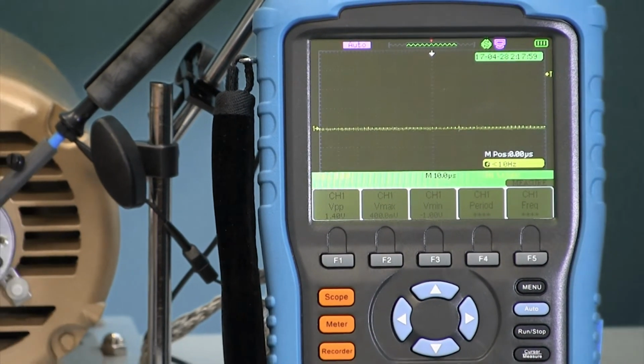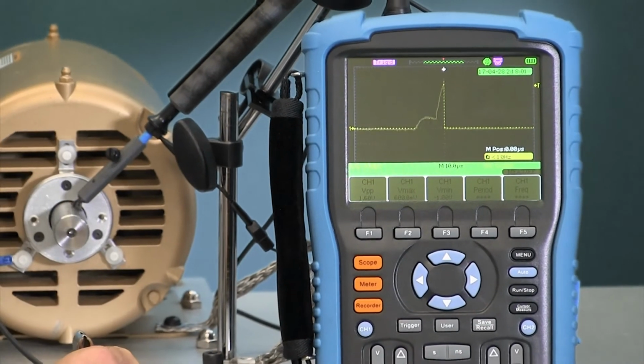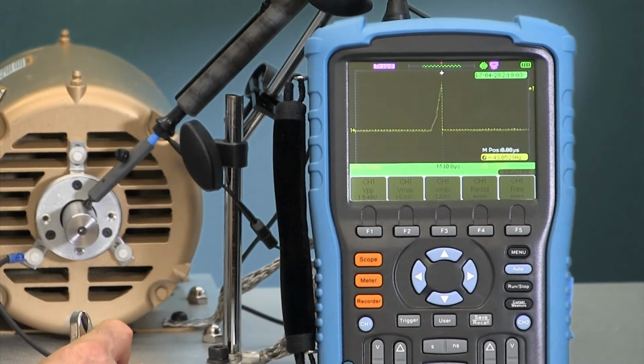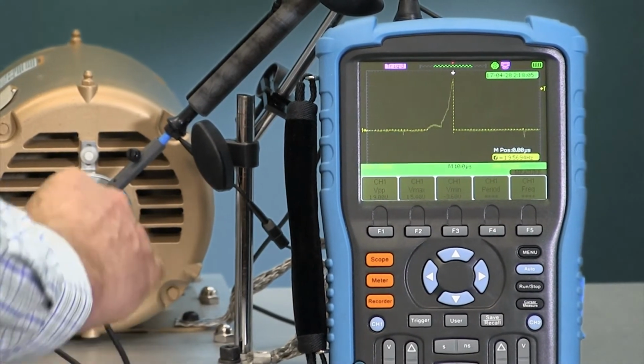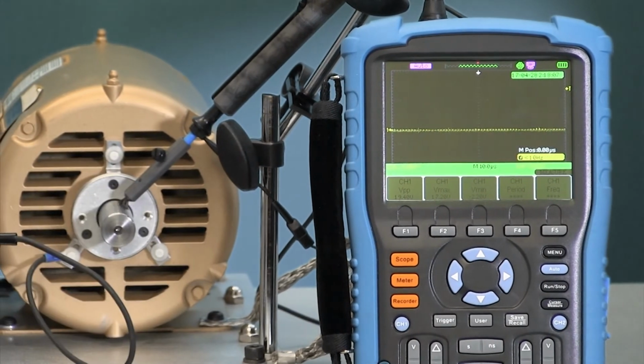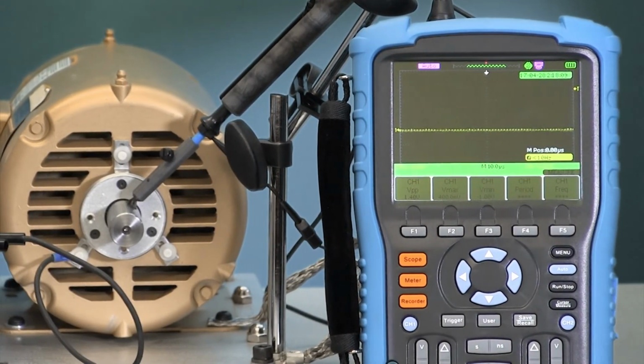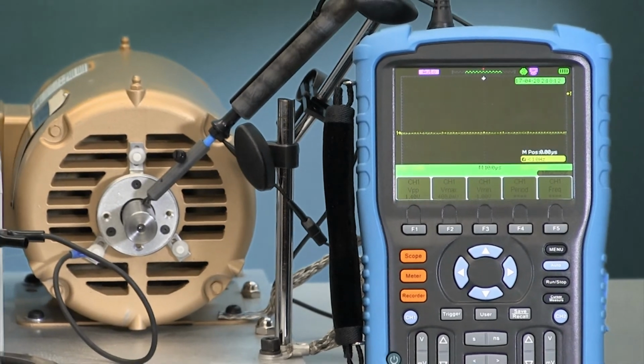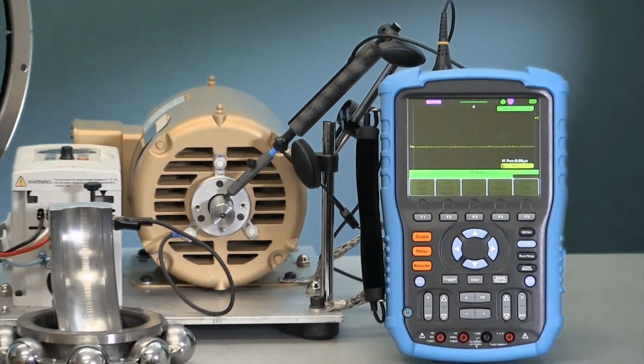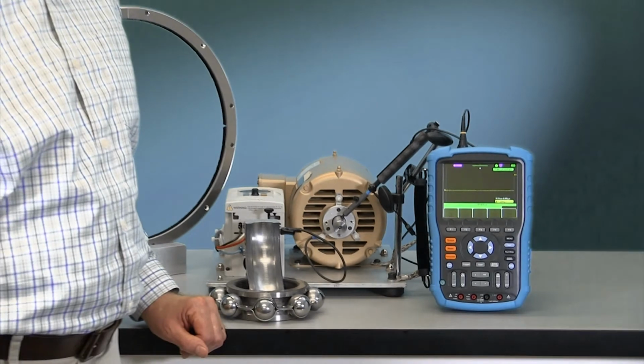So you can see when I take the shaft grounding ring back out of service, the voltage immediately comes back and you get bearing discharges. I connect it back to ground and the bearings are protected again.